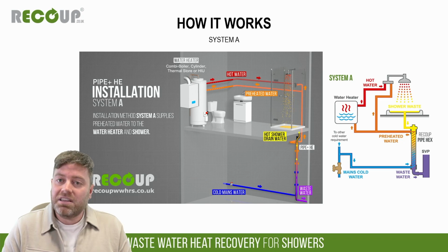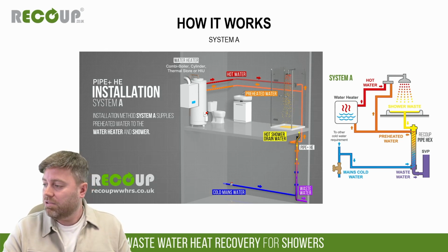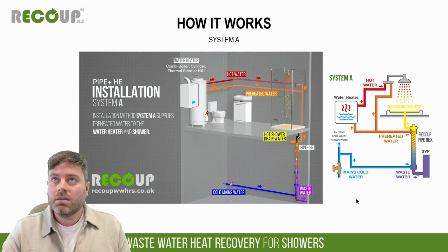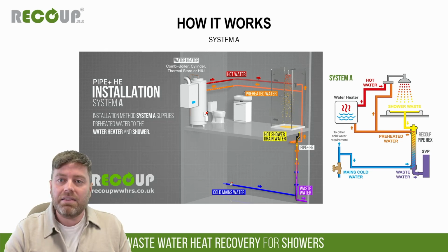And then because you're sending preheated water also to your water heater, the hot water you are using is now only being heated up from about 25 degrees, as I say, rather than from 10 degrees. So the hot water you are using is requiring less energy to produce it. So that's the most efficient method, System A. As I say, that's not always applicable or not always able to be used. So, for example, where you've got centralised hot water, you wouldn't be able to use System A because you can't be sending all your preheated water back to your sort of centralised hot water plant or through multiple wastewater heat recovery systems. So where you can't use System A, the second system we normally look at is System B.